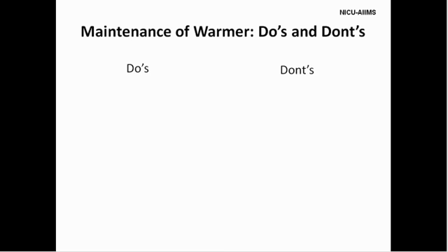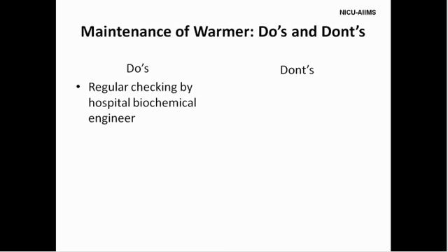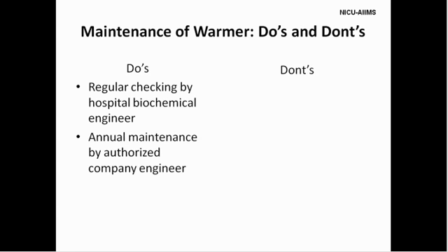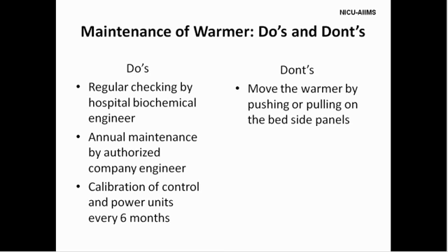Now let us see some regular maintenance tips. There should be regular checking by the hospital staff and also annual maintenance by the authorized company engineer. Calibrate the control unit and the power unit every 6 months. What should we not do? Do not move the warmer by pushing or pulling on the bedside panels. Do not put anything on the top of heater assembly, and ensure that the caster wheels are not locked while you are moving the radiant warmer.